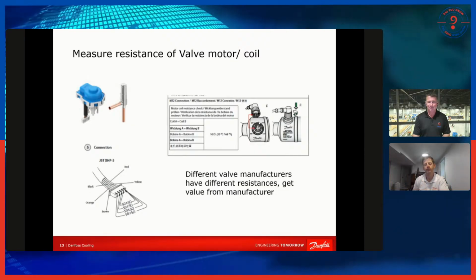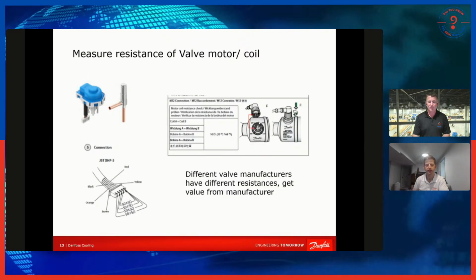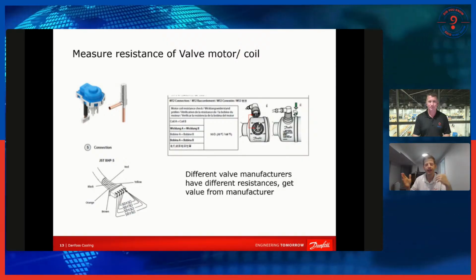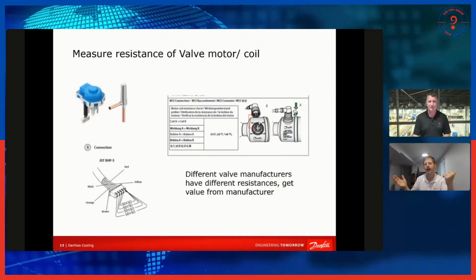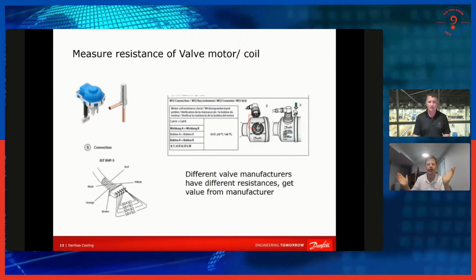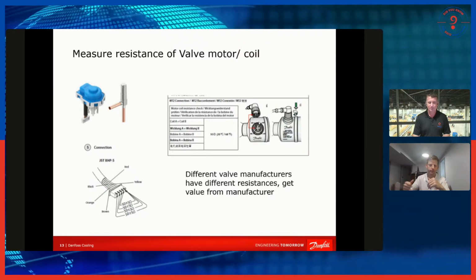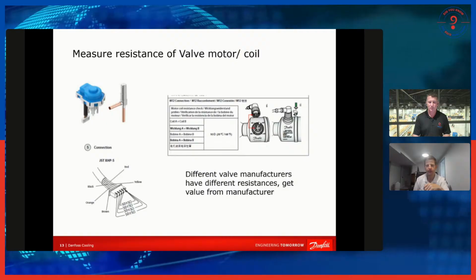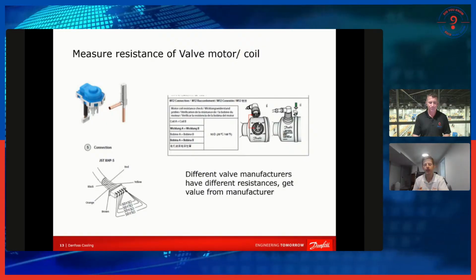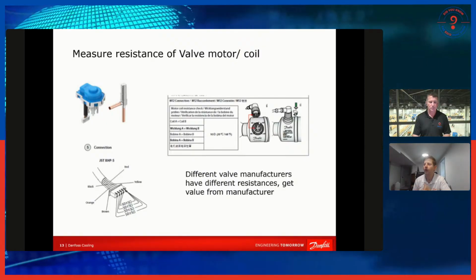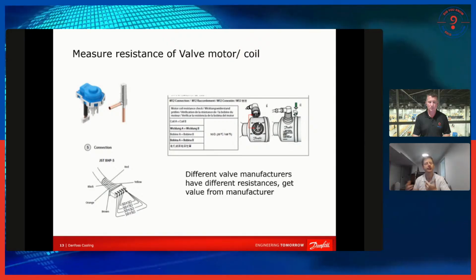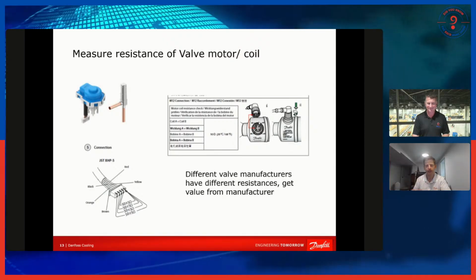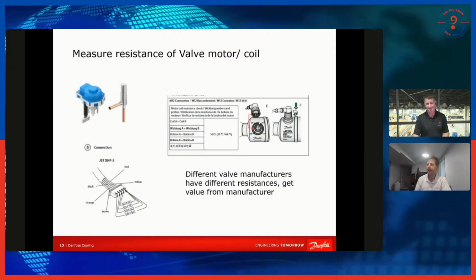You get a high superheat alarm because the valve is 100% open and it can't do anything to bring the superheat down. It's been high superheat for 2 hours, and now the chiller is kicking out an alarm for high superheat. Just sort of depends. So that's a way you can find things. But the EXV is a dumb valve. It only does what it's told, and it relies on the controller to know where it's at.